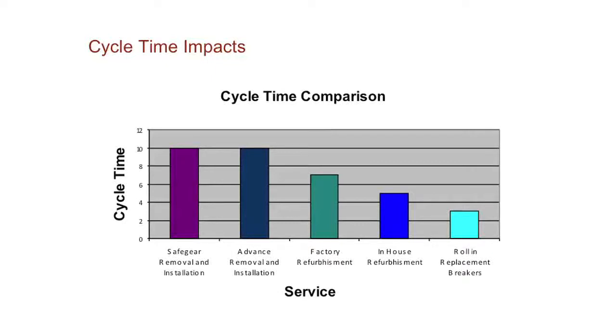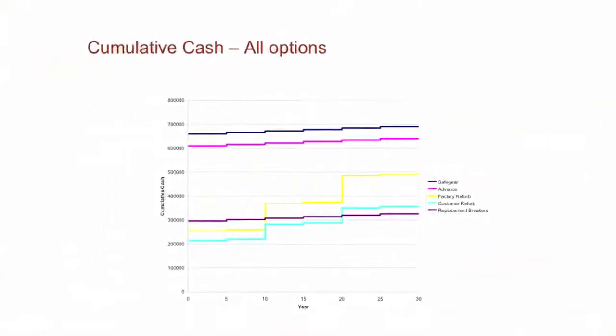When we look at these other ones, of course, they're cheaper options, but at the end of the day, what do you got? You got the old gear, you got the old breakers. We put the new relays in, we put the arc flash mitigation, but that's all we did here. And then when you look here, it's like putting a new engine in a car. For $320,000, you've got the arc flash mitigation, brand new relays, brand new breakers, and you basically extended the life. This is what I was talking about before when I said that we can show you over the course of time what it would cost you.